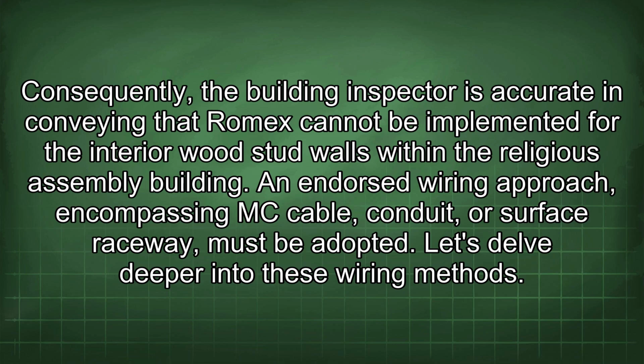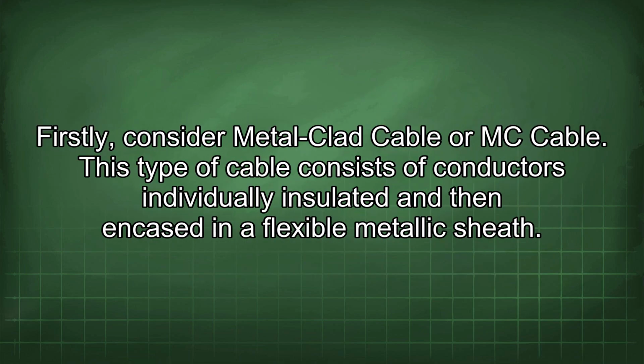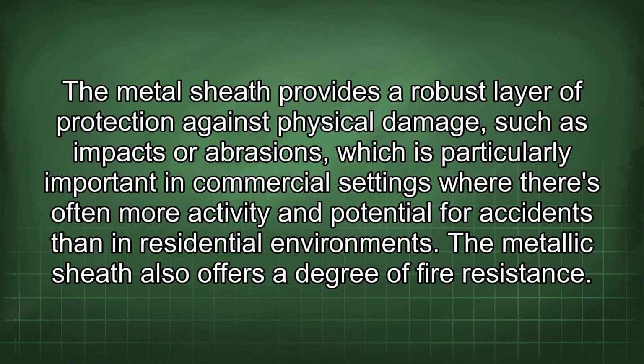Let's delve deeper into these wiring methods. Firstly, consider metal-clad cable, or MC cable. This type of cable consists of conductors individually insulated and then encased in a flexible metallic sheath. The metal sheath provides a robust layer of protection against physical damage, such as impacts or abrasions, which is particularly important in commercial settings where there is often more activity and potential for accidents than in residential environments. The metallic sheath also offers a degree of fire resistance.